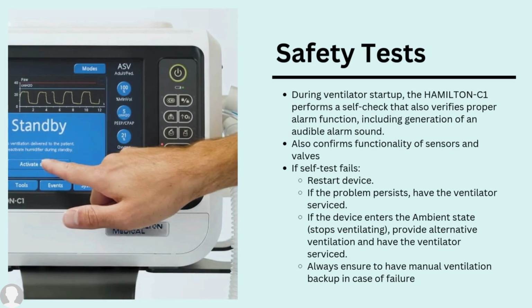There are various safety tests incorporated into the Hamilton C1 to ensure that the ventilator operates safely and delivers effective respiratory support. During the ventilator setup, the Hamilton C1 performs a self check that also verifies proper alarm function, including generation of an audible alarm sound. It also confirms functionality of sensors and valves.